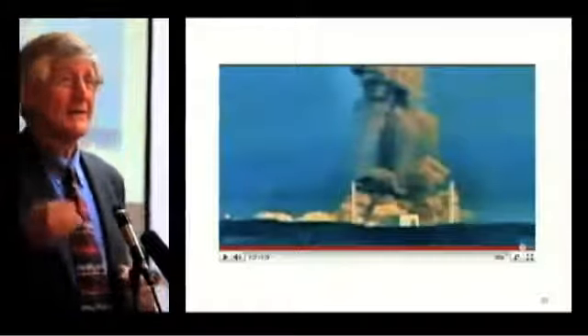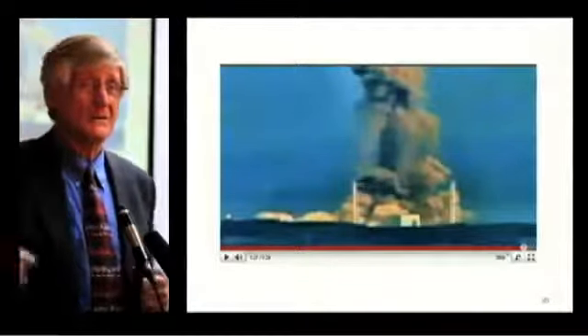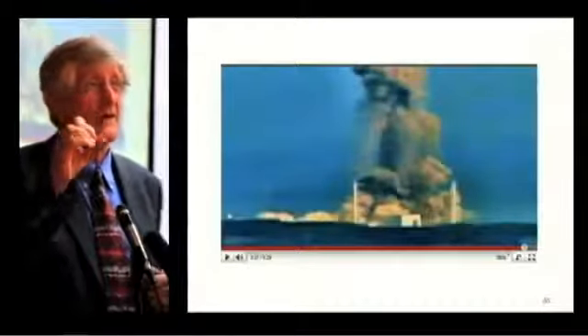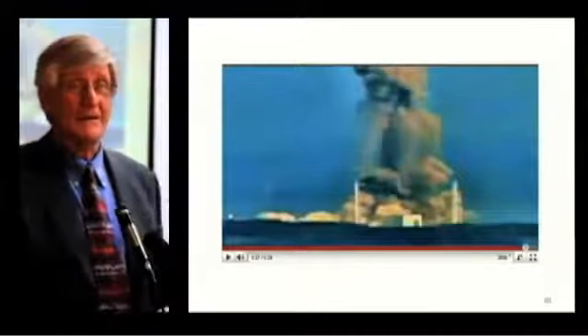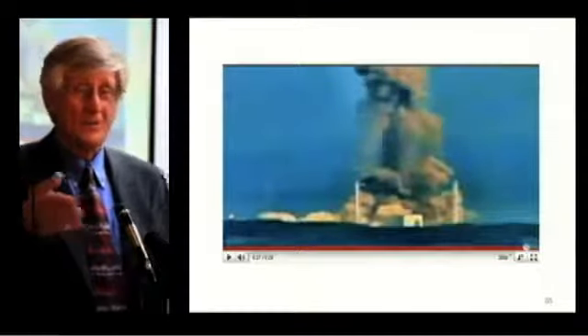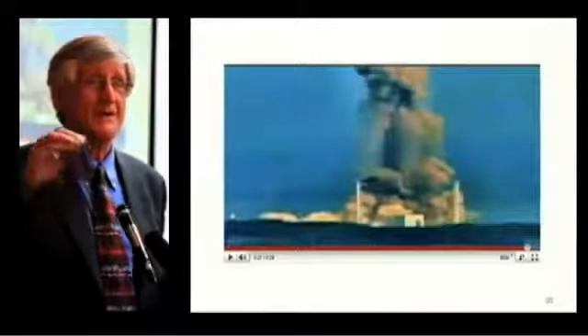And I calculated again how much energy it would take to throw something like that in the air, which would have some air resistance. And even if it was a perfect sphere, which had very little air resistance, it still would have had to be thrown at around 1,000 miles an hour, which again indicates that this was a detonation, not a deflagration. I think the nuclear industry is going to argue to downplay the significance of that, but the difference between a detonation and a deflagration is dramatic in containment design.